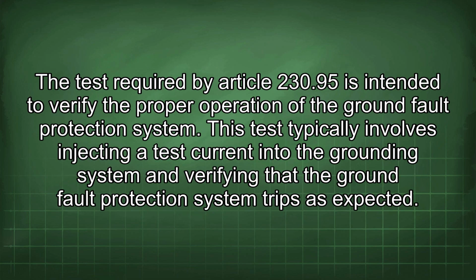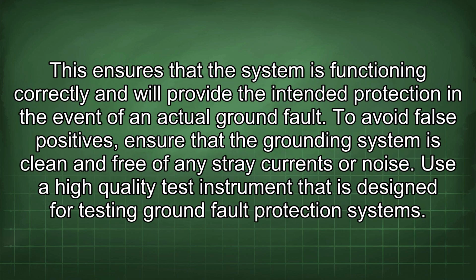The test required by Article 230.95 is intended to verify the proper operation of the ground fault protection system. This test typically involves injecting a test current into the grounding system and verifying that the ground fault protection system trips as expected. This ensures that the system is functioning correctly and will provide the intended protection in the event of an actual ground fault.